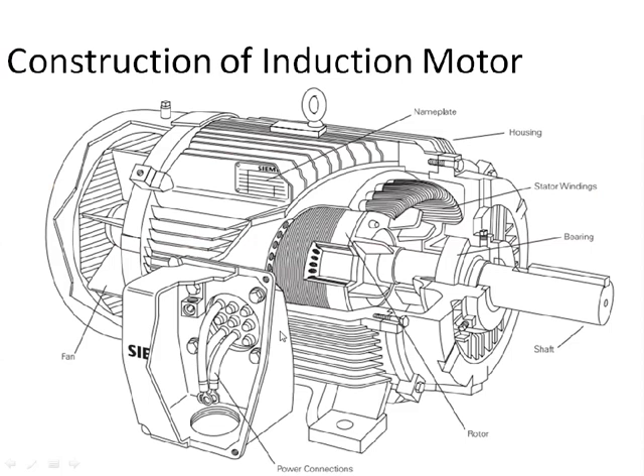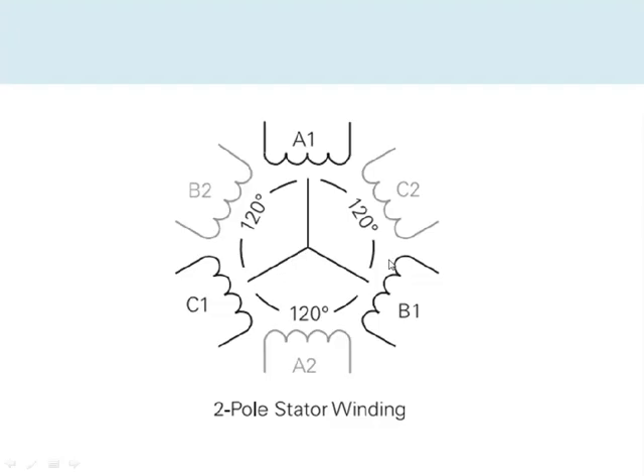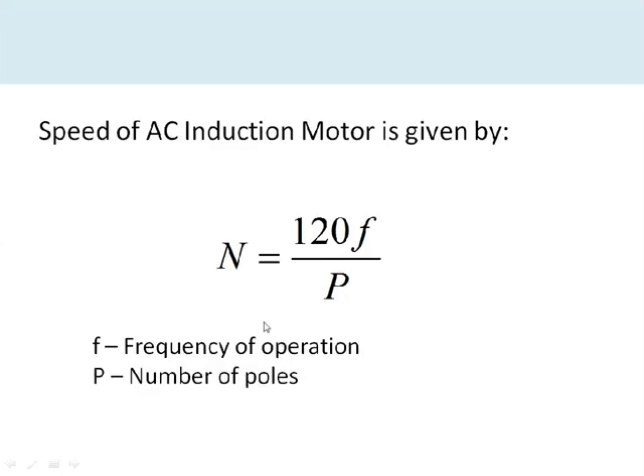This is the construction of a typical induction motor. The stator windings and rotor are the important parts. When power is applied to the stator winding, a rotating magnetic field is generated, which interacts with the rotor and causes it to rotate. The number of times each stator phase winding repeats defines the number of poles. Here, a particular phase winding is repeated two times, making this a two-pole, three-phase induction motor.